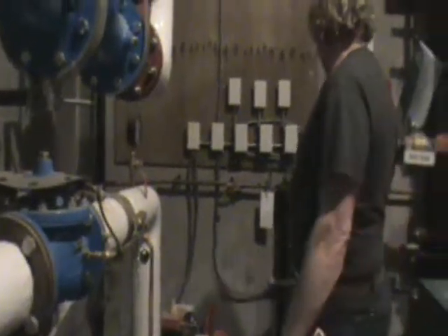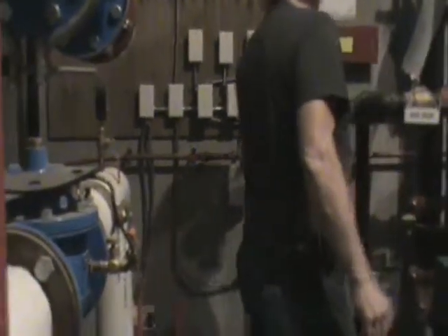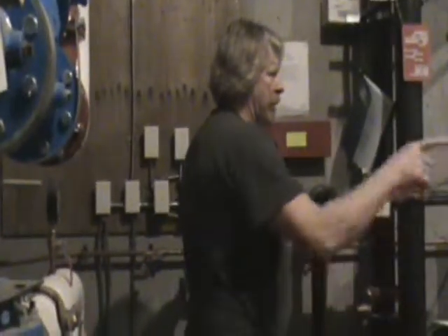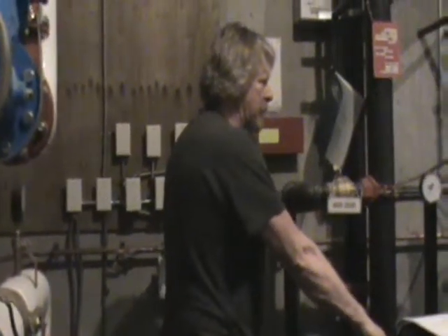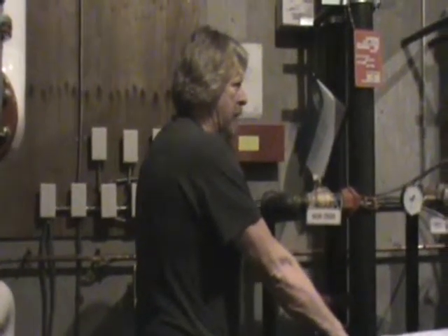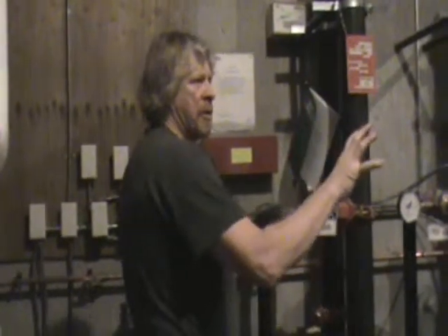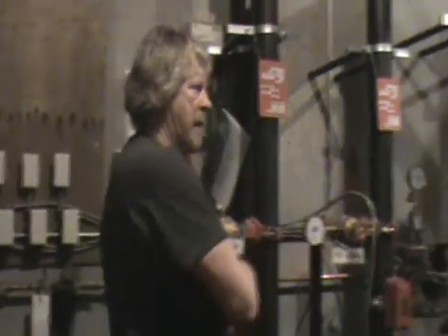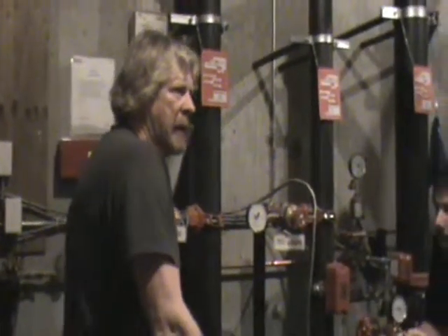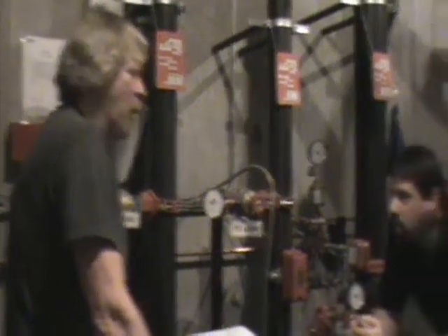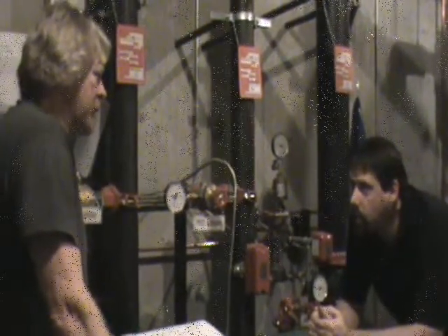There's another one here. These backflow preventers, that one and this one, have to be tested once a year. You'll probably get a notice from the city to get them done. And what are those for? This one here is the water supply for the boilers, right? There's hardly ever any water going through that because that's a closed system. It's got chemicals and everything in it. That's why it has a backflow preventer on it. Is it a glycol? No, just cleaning chemicals.